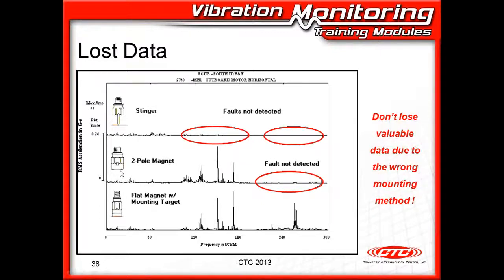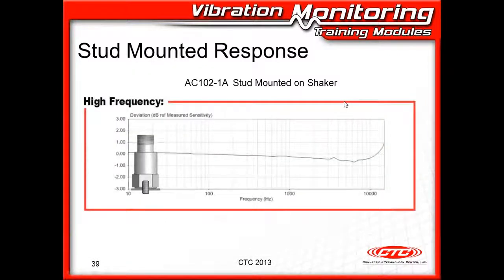At the same time, if we measure the same machine, same position with a two-pole magnet, you can see that we picked up the mid-frequencies, but the high frequencies were still missing. And then when we came back with our flat magnet and our mounting target, we were able to see the entire story. We got to see all the vibration, not only the low vibration, but the mid frequencies and the high frequencies. So be very careful with your mounting methods that you're not losing valuable vibration data. Know that when you put something between the sensor and the machine, it's going to affect the frequency response, and it's not going to make it better, it's going to make it worse every time.